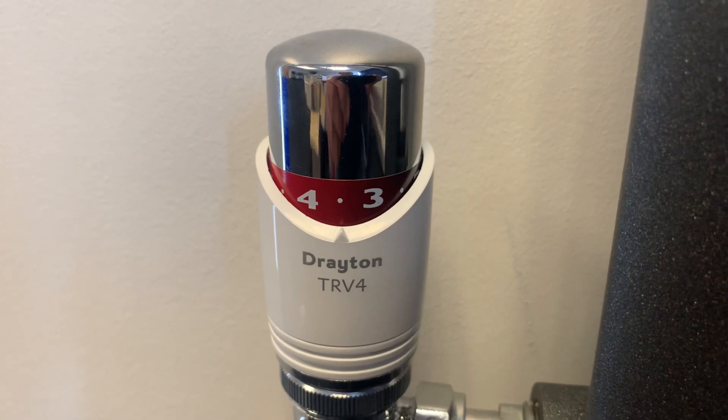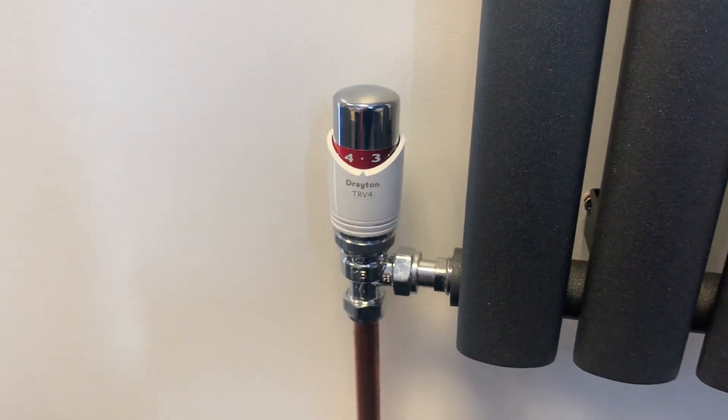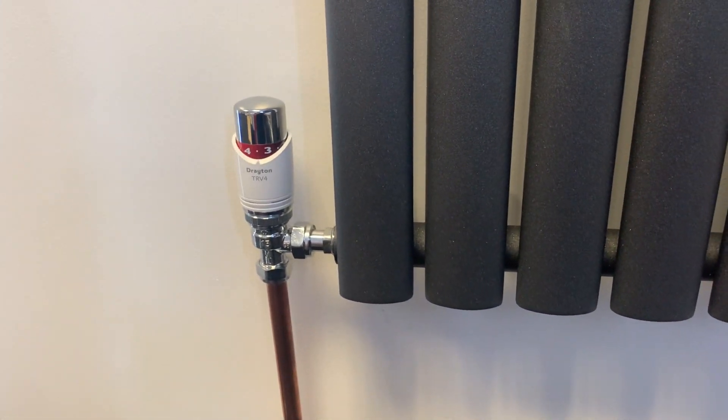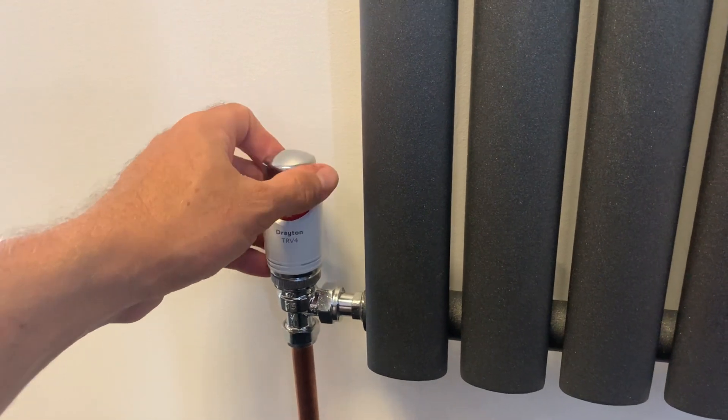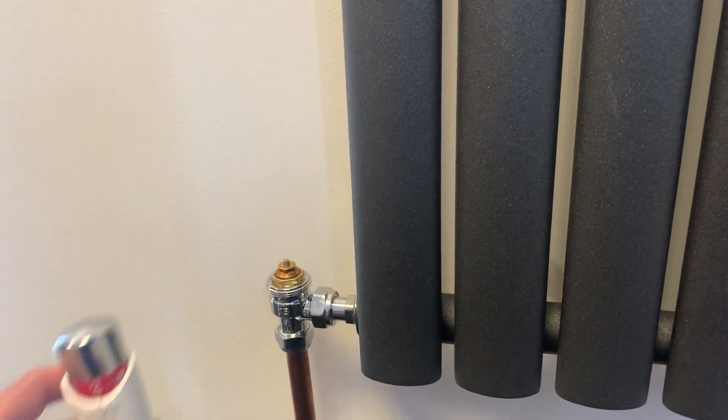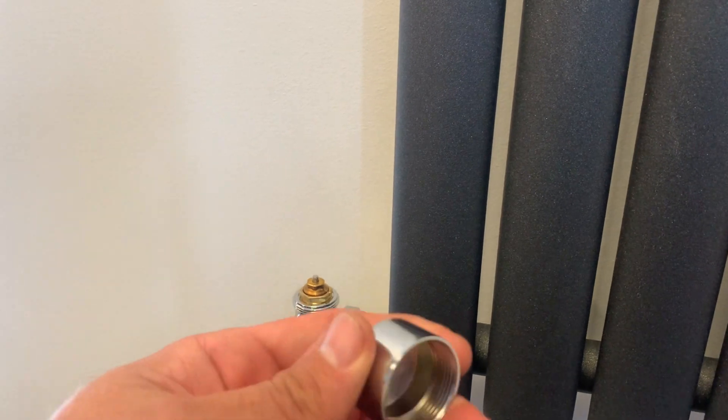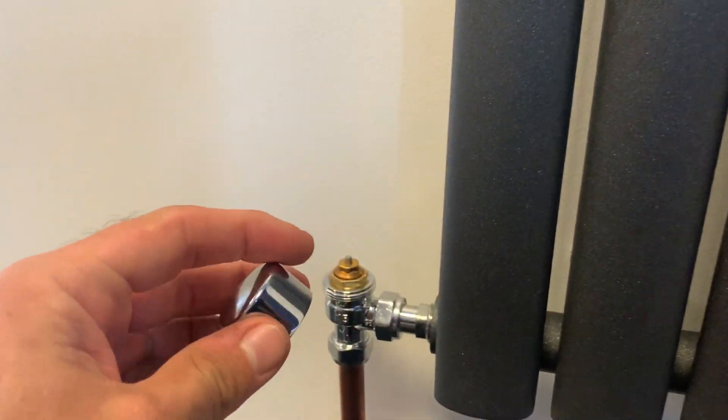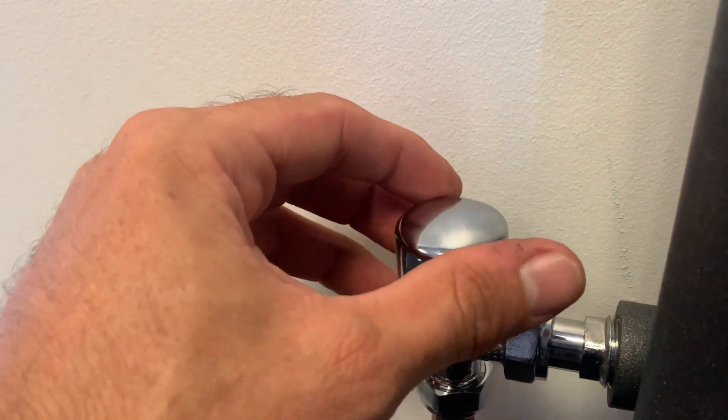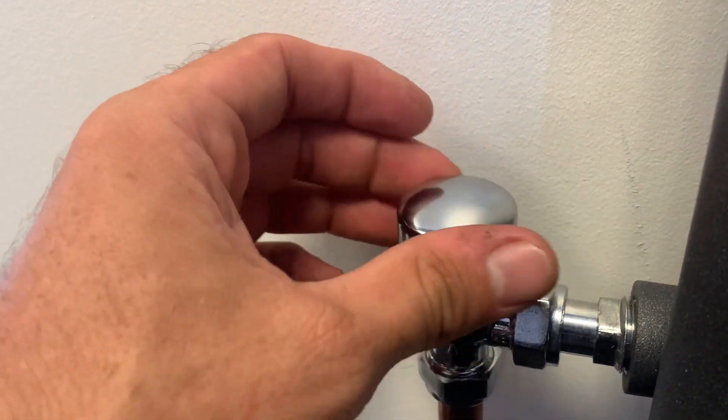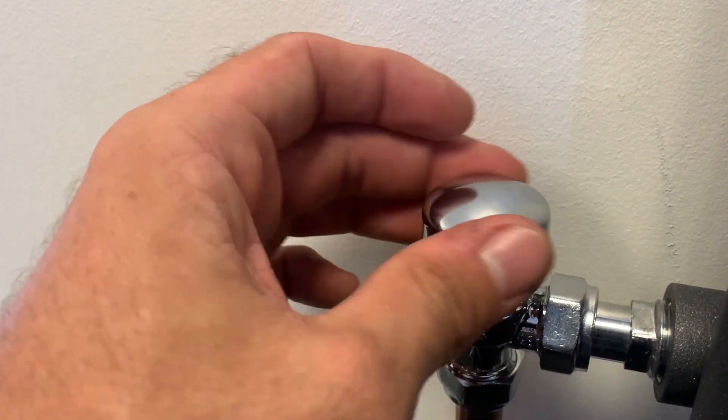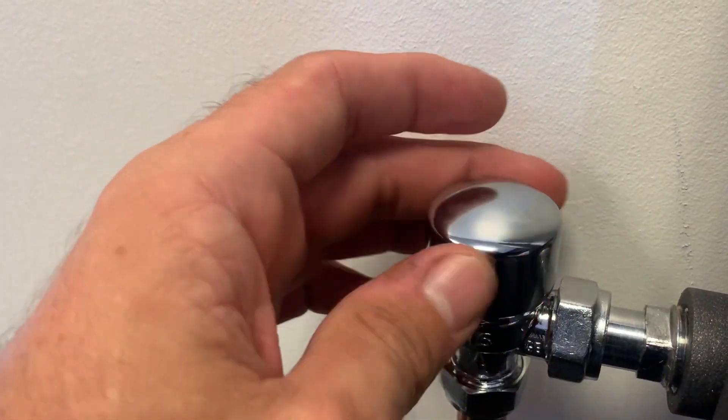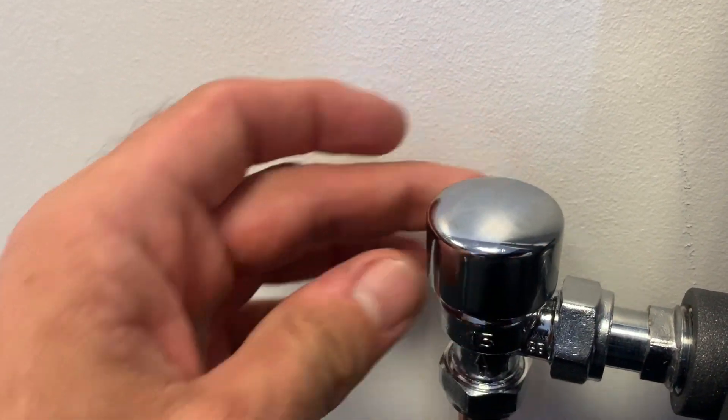When specifying the auto balancing valve we recommend fitting on all radiators even if you don't intend on fitting a TRV, as it's important to ensure consistent flow into all radiators on the system. If you need to leave one open for bypass purposes simply fit a decorator's cap. Just be sure to only screw it down until it just touches the top of the pin, don't screw it all the way otherwise you'll restrict flow into the radiator.